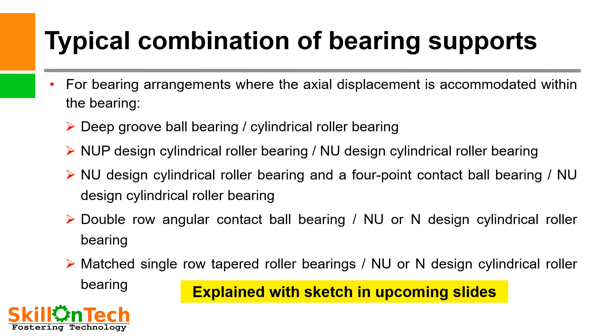Typical combination of bearing supports for arrangements where axial displacement is accommodated within the bearings includes: deep groove ball bearing with cylindrical roller bearings, NUP design cylindrical roller bearings with NU design cylindrical roller bearings. The four-point contact ball bearing's outer ring will be free to accommodate axial load. If provision for axial displacement is not kept, the axial load will impact on the bearing and the bearing may fail.